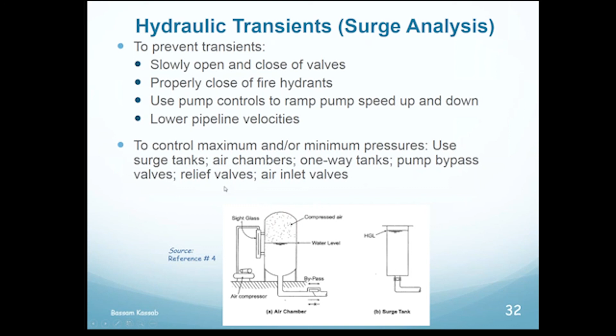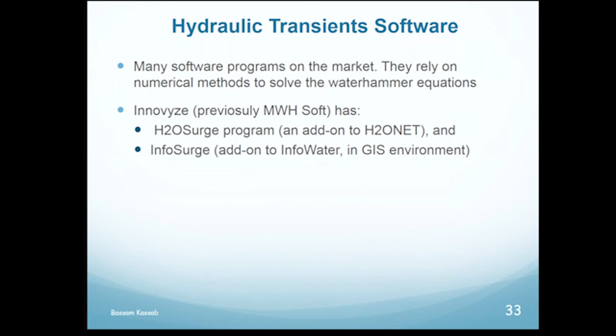And there is a lot of software for hydraulic transients. I'm only familiar with those two, H2O Surge and InfoSurge. This is an add-on for H2ONet, and this is an add-on for InfoWater, which uses a GIS environment. But there are many others out there in the market. All are good. You just need to learn one of them and learn it well. And again, my advice is to calibrate your network well first before you go into the surge analysis. It has to be calibrated for steady state before you even start doing the surge analysis.